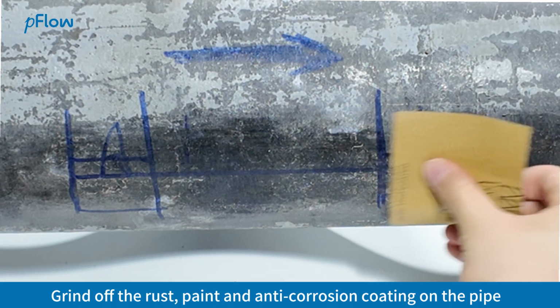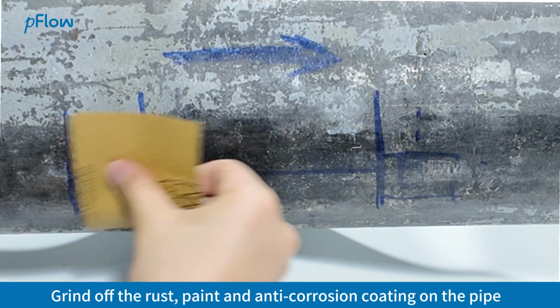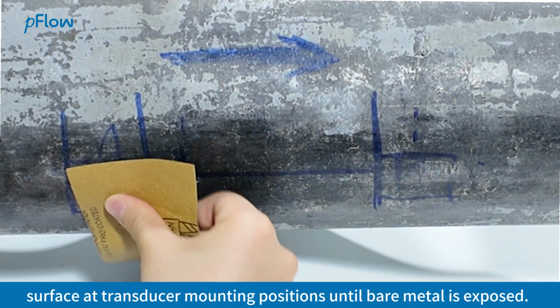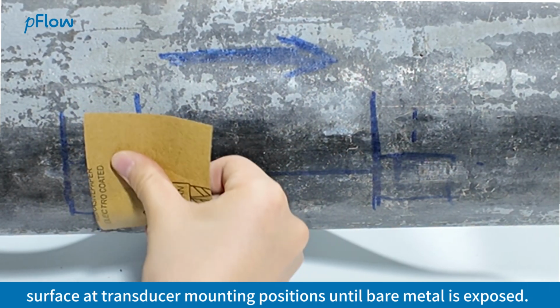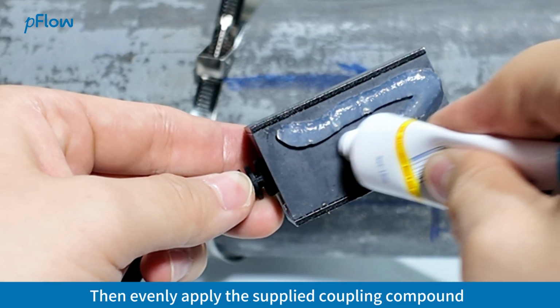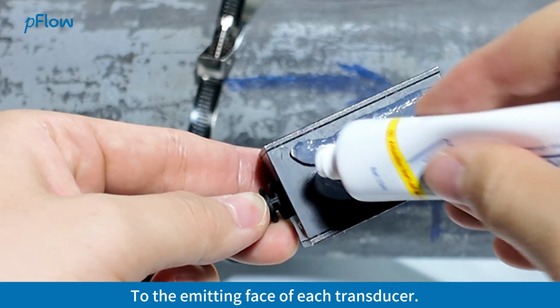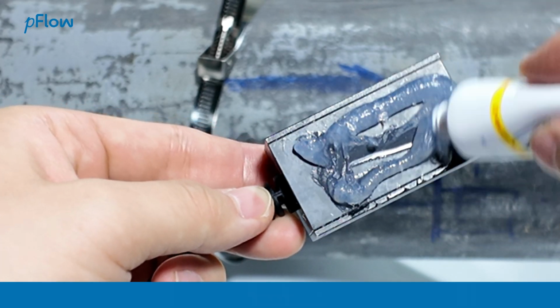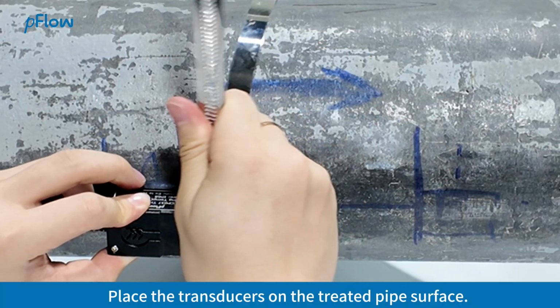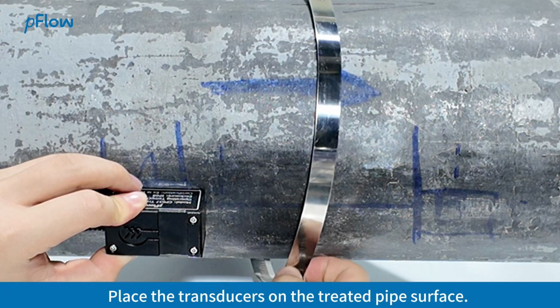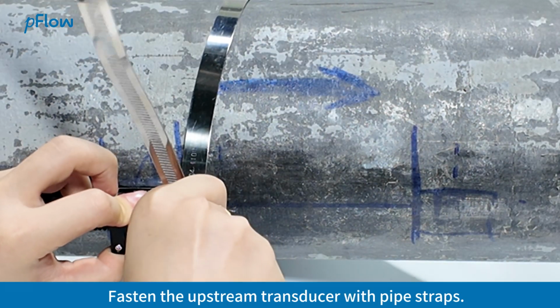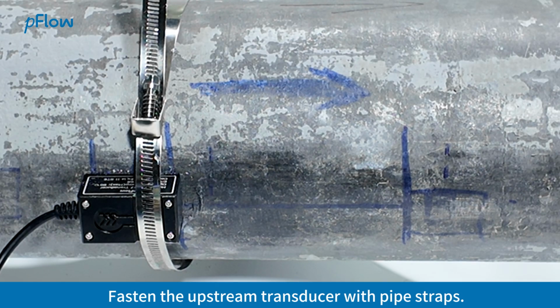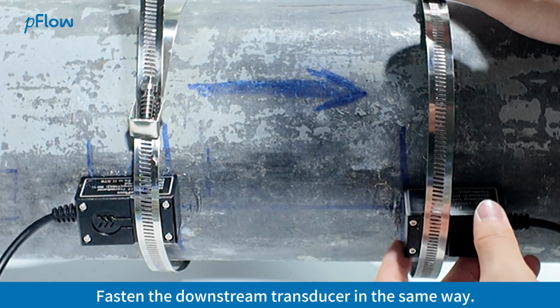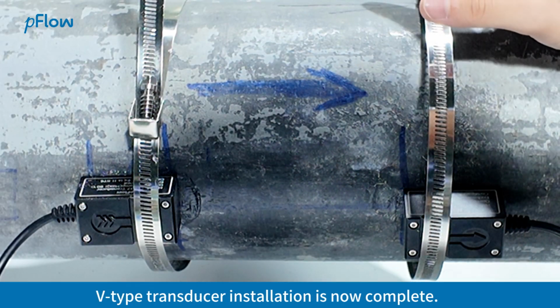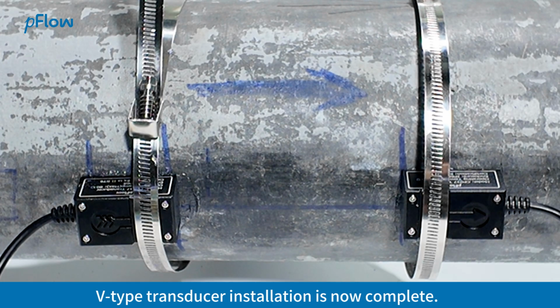Grind off the rust, paint, and anti-corrosion coating on the pipes. Surface at transducer mounting positions until bare metal is exposed. Then evenly apply the supplied coupling compound to the emitting face of each transducer. Place the transducers on the treated pipe surface. Fasten the upstream transducer with pipe straps. Fasten the downstream transducer in the same way. V-type transducer installation is now complete.